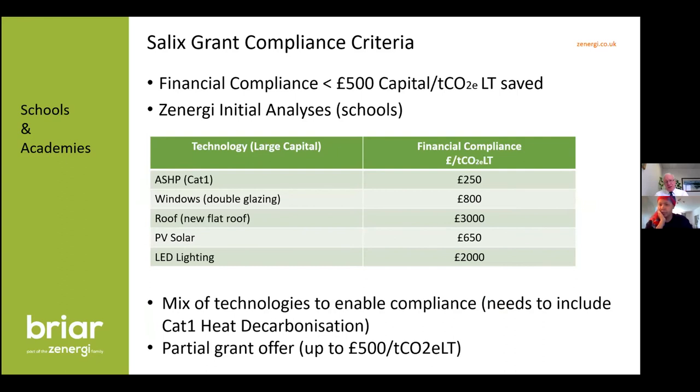The financial compliance criteria is £500 of capital contribution per tonne of CO2 saved over the lifetime of the technology. Analysis on primary schools — the worst case scenario, open heating from 8am to 4pm five days a week — shows air source heat pumps get well over the line at £250 per tonne of CO2. But windows come in at £800 — 60% above the £500 threshold — and flat roof insulation is very expensive and will not be fully covered, so you'd be looking at partial grants for those measures.